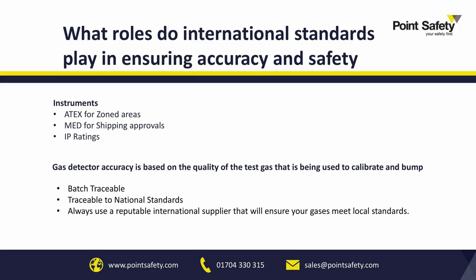Again, moving on to international standards. Every country and every region will have independent national standards relating to the use of gas detectors. So we won't really go into that area, but each instrument will have a rating for ATEX for zoned areas. Typically 90% of units are used within zoned applications, or the potential for zoned areas. So you will find that most instruments are rated for at least ATEX Zone 2 and above.